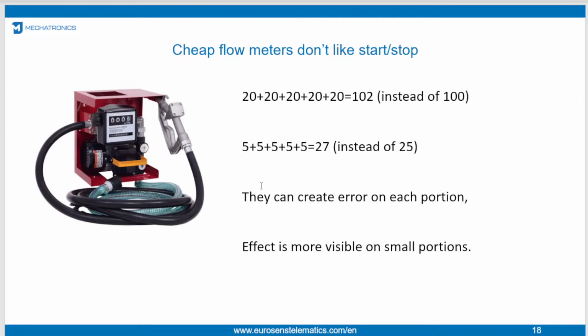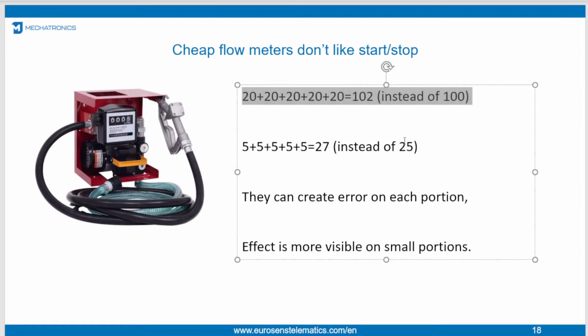At first, it depends on what equipment you use for tank calibration. Cheap fuel counters don't like start-stop, and you can have about half a liter of error per portion. So when you're using cheap fuel metering equipment, smaller portions of 3-5 liters may lead to less accuracy due to start-stop error. In fact, you can test it: make a comparison with your fuel metering equipment, try to fill 50 liters with big and small portions and see the result.